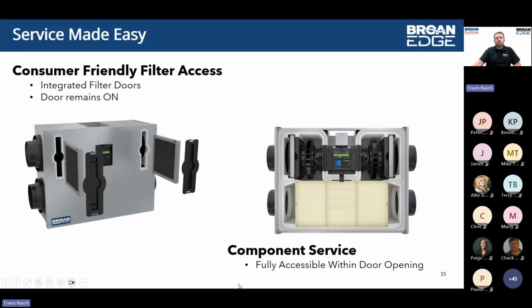Craig, I did see you put your question in the chat, so let me go to that quick and see if it's relevant to what's on the screen here. Being in a small mechanical closet, we receive calls where there are hard elbows directly off the units, causing airflow and related error codes, i.e. blower drive feedback, when ductwork at the plenum is too close, space challenges. Will these units have a similar potential issue?